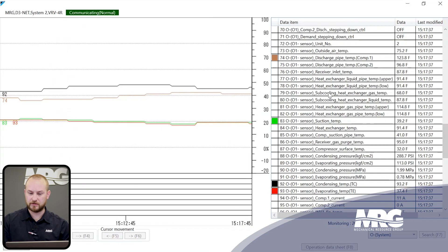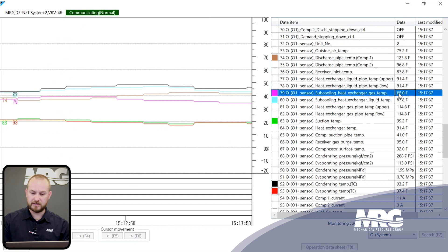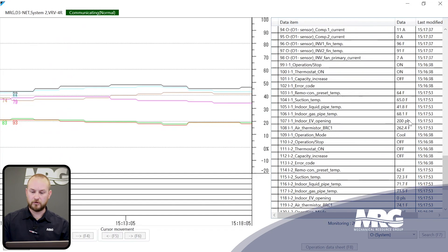The most common offenders are going to be indoor units and subcooling EEVs. We'll look at our subcooling heat exchanger gas temp and liquid temp first. In basic terms, a 68-degree gas temperature cannot equate to a 39-degree suction temp, so we know the subcooling circuit is not our culprit. We need to look a little bit further.